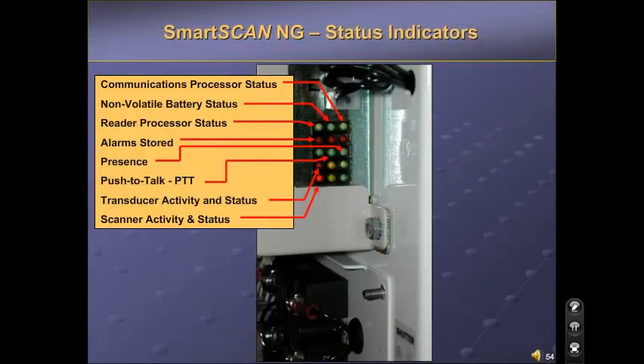On the side of the NG interface module is a bank of indicator lights. The label on the metal cover should show the identity of the lights. A full description of the lights can be found in the user's guide. The two lights on the top row are for the dual processors. The COM processor and reader processor lights should be turning on and off in a slow, steady pattern. These lights indicate that both processors are running correctly.